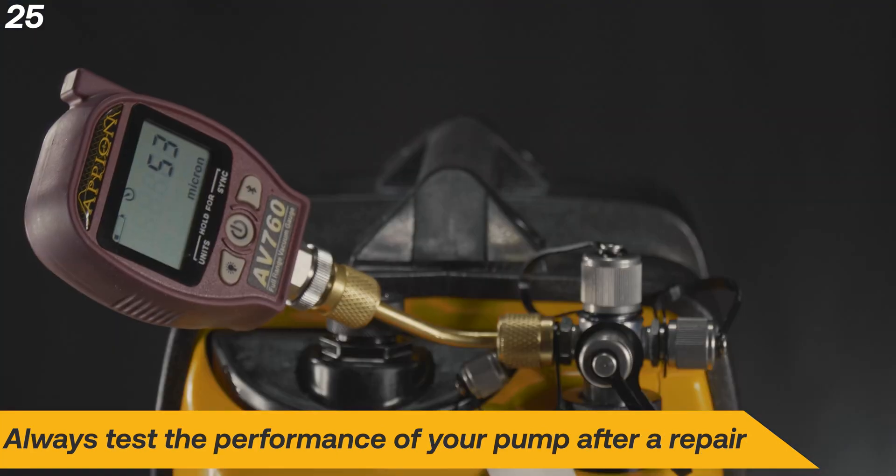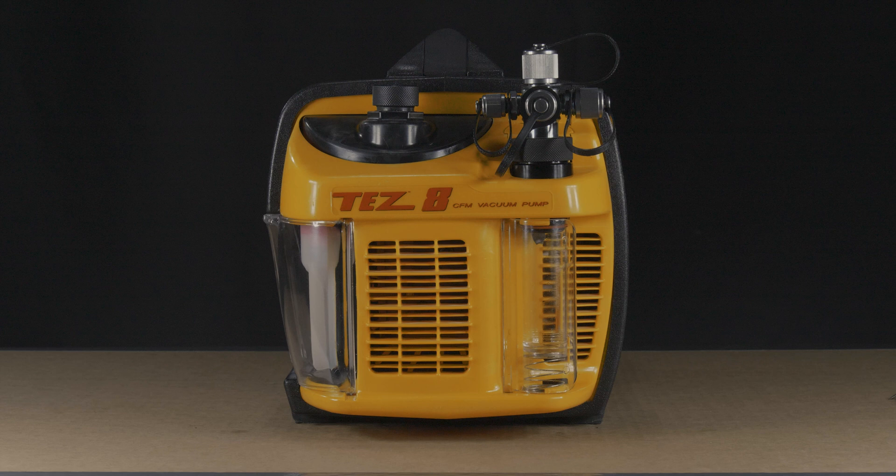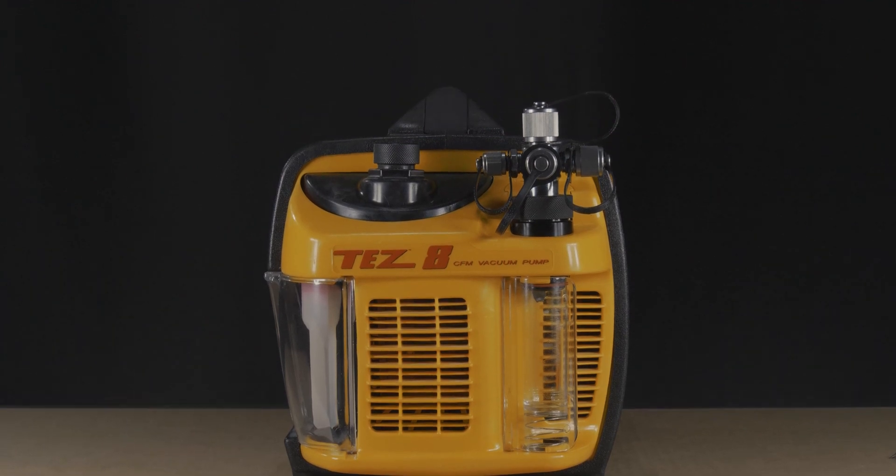After the repair, run a test on your TEZ 8 pulling down to 50 microns to ensure that the repair was successful. The parts in this kit are easy repairs to remedy a vacuum leak and can often bring a pump back to life without the difficulty of a full internal rebuild. If you have any questions about any repair, don't hesitate to reach out to Appion directly.